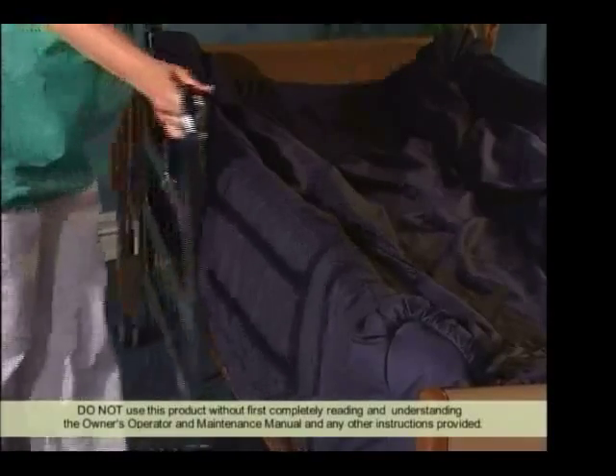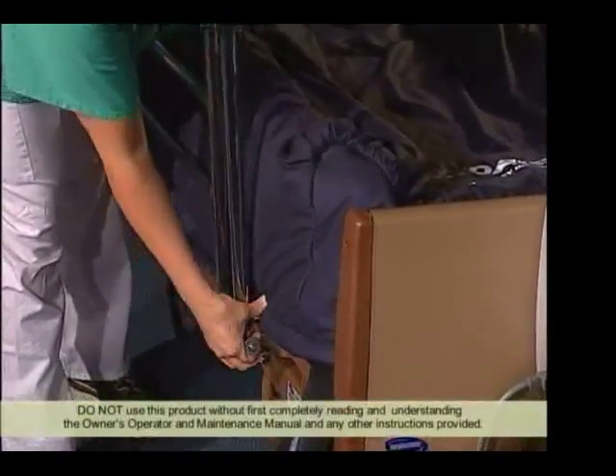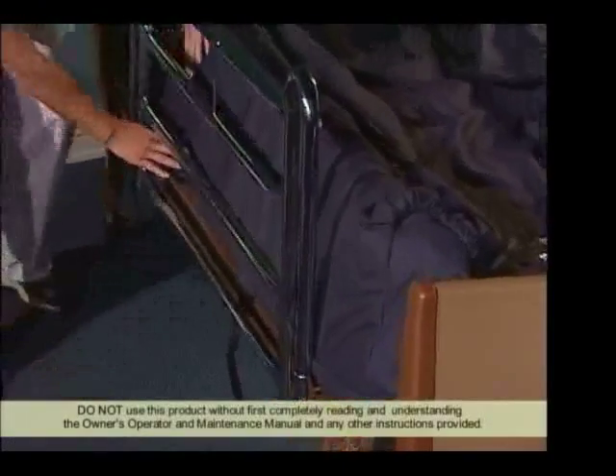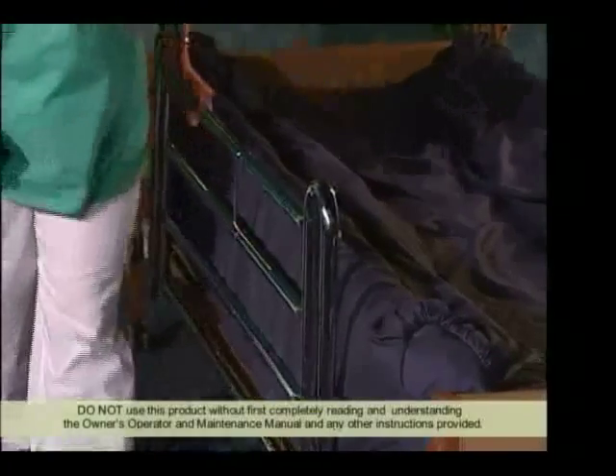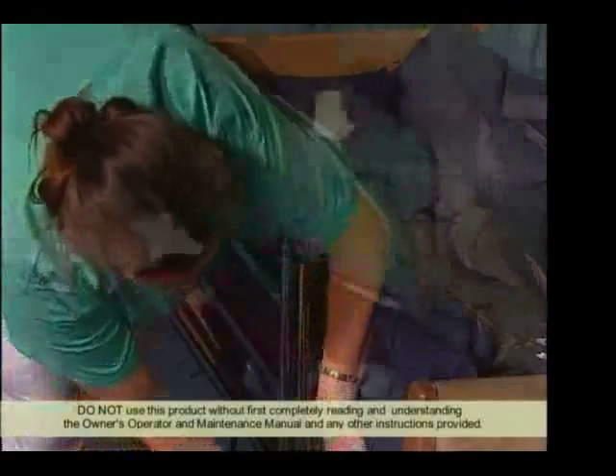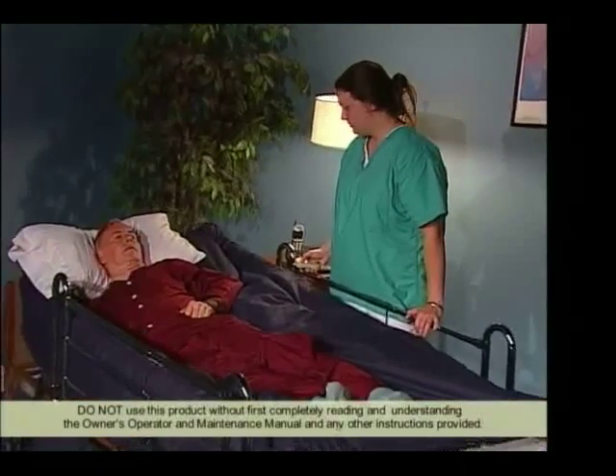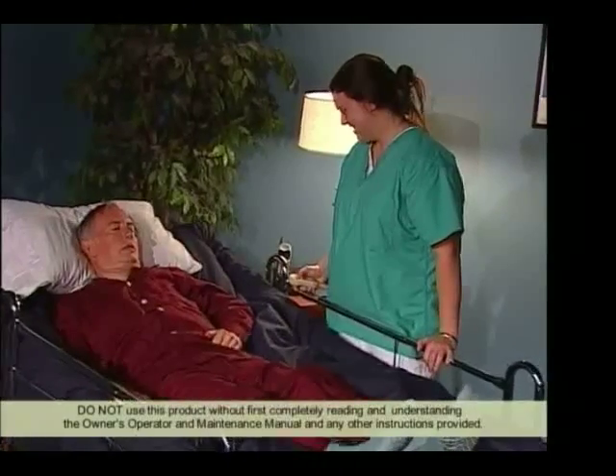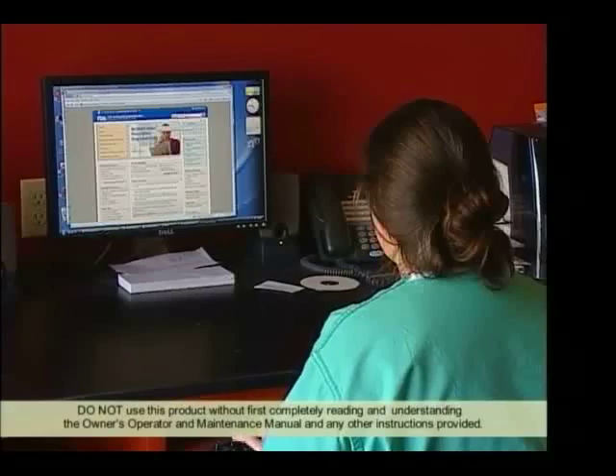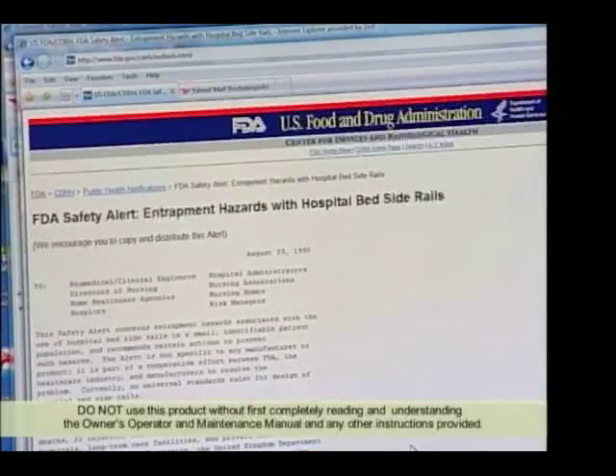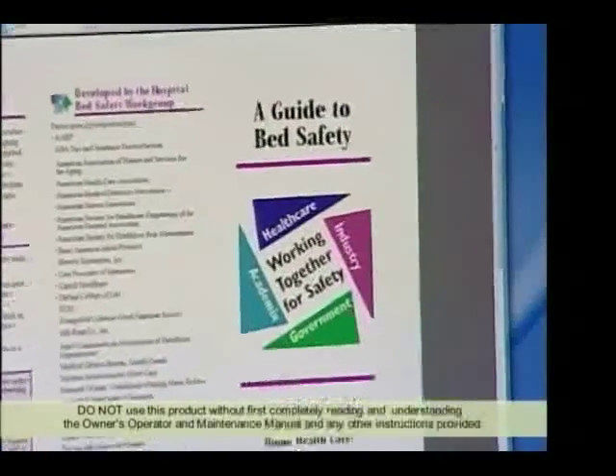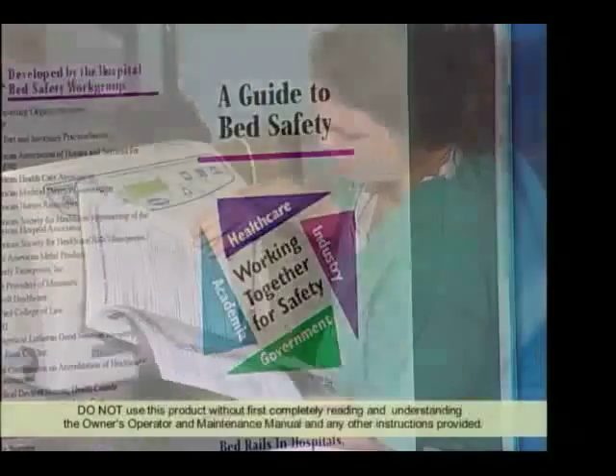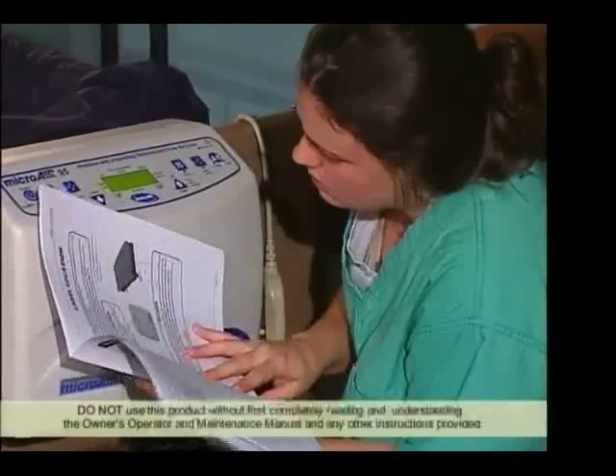After any adjustments, repair, or service, and before use, make sure all attaching hardware is tightened securely. Assist rails with dimensions different from the original equipment supplied or specified by the bed manufacturer may not be interchangeable and may result in entrapment or other injury. Monitor the patient frequently. Proper patient assessment, monitoring, and maintenance and use of equipment is required to reduce the risk of entrapment. Visit the FDA website at www.fda.gov to learn more about the risks of entrapment, and review a guide to bed safety published by the Hospital Bed Safety Work Group located on Invacare's website at www.invacare.com. Refer to the Owner's Operator and Maintenance Manual for additional product and safety information.